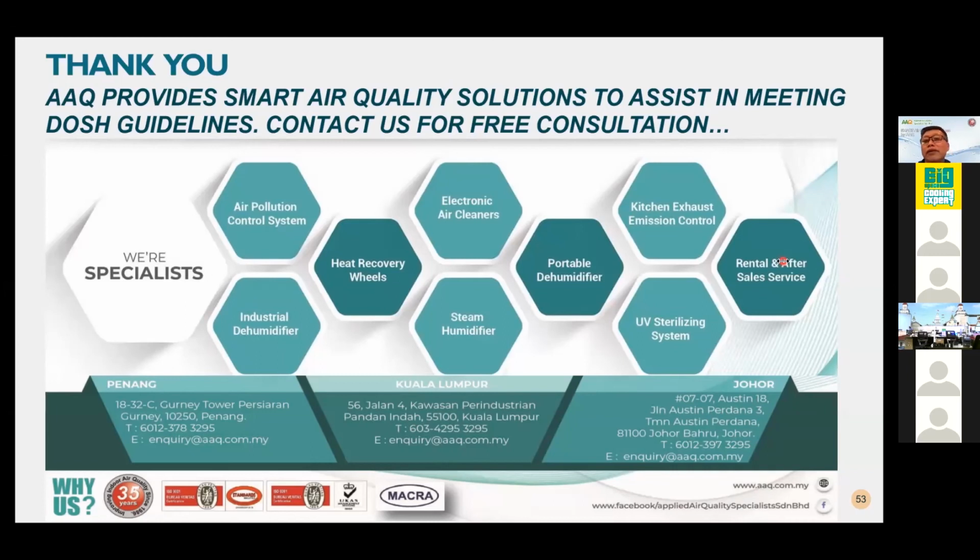Agree, but I think I have to carry out an evaluation on the heat recovery system. As long as you do an evaluation and air sampling to test whether it will affect during this pandemic, because the only thing we are worried about is cross air contamination on the heat recovery wheel, because it uses the same rotor, so it is turning.